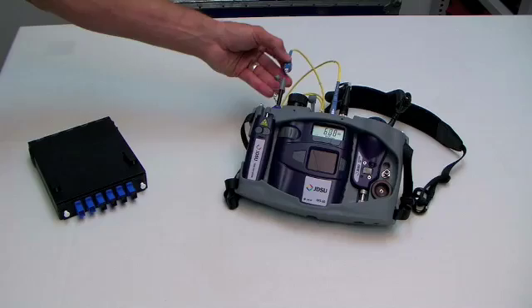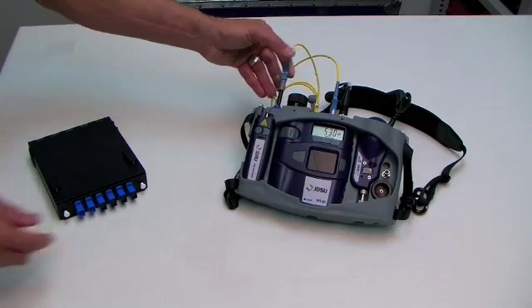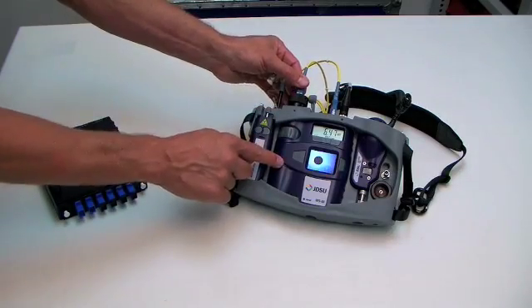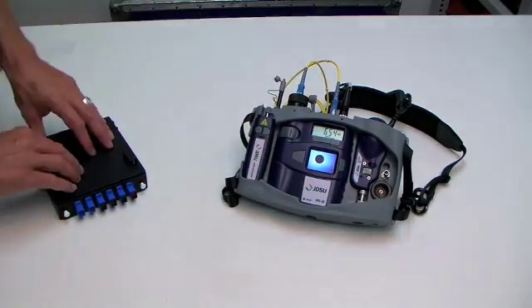I pull the test lead out, I put it into the cleaning tool that's held in the carrier, give it a couple cleans, put it back in the patch cord viewer, and I can see that my test lead is clean.